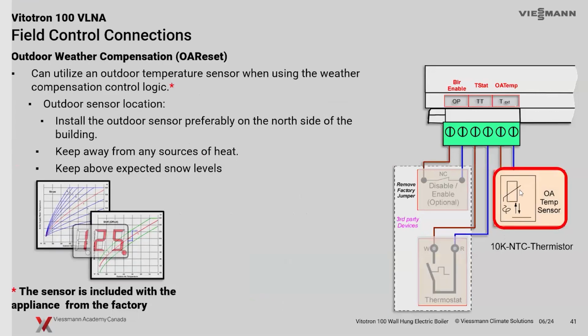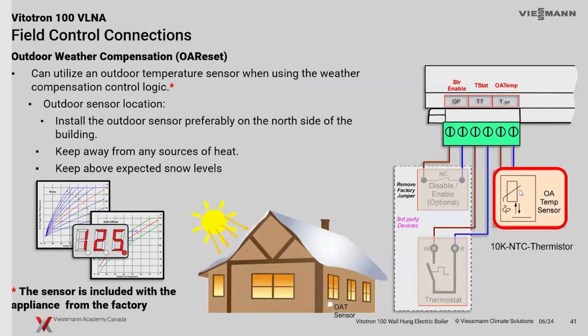Then off to the right-hand side on that same terminal strip, we have the outdoor air temperature sensor, or external temperature sensor, just a 10K NTC, which is the same as all of our current outdoor sensors we use on our Vitotron 100s, 200s, and our current boiler product line on the gas side. So same resistance or thermistor, 10K NTC. And should you want to use outdoor reset, always advisable, it reduces the number of elements coming on during the shoulder seasons and will save you a little bit of energy and power.